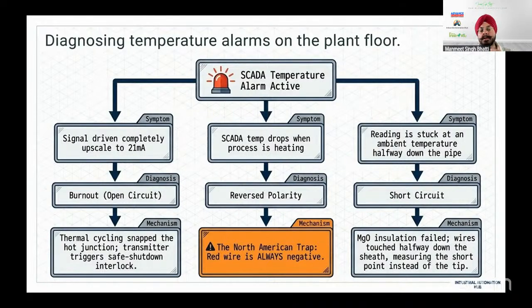What is happening is thermal cycling snapping the hot junction. Now it has gone into the safe shutdown interlock. This is one reason. The second thing is, SCADA temperature is going down, but your process is heating up. It's basically nothing else. It's a reverse polarity.